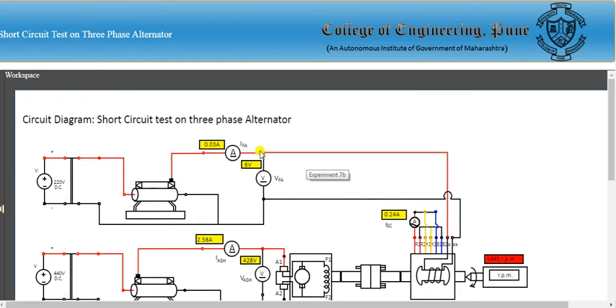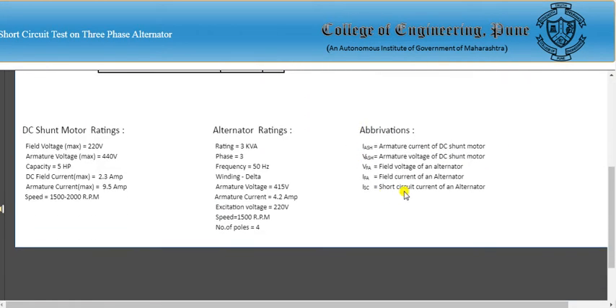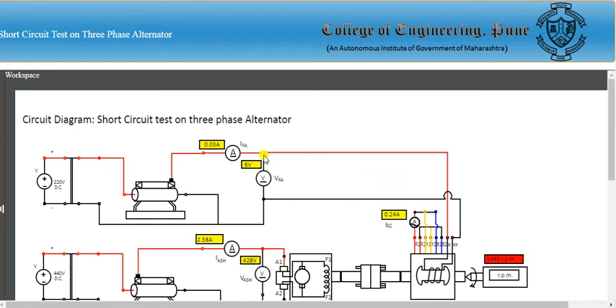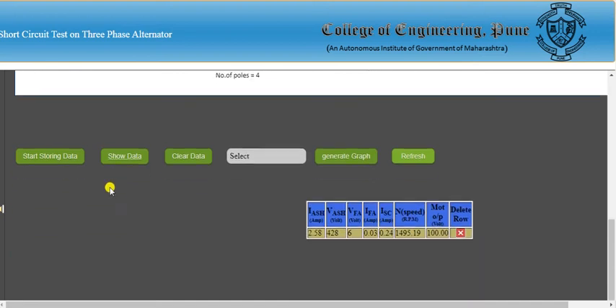The DC field current is increased until the short circuit current (armature current) reaches the rated value of 4.2 A. The alternator ratings are shown on screen — rated voltage is 415 V and rated armature current is 4.2 A. Keep storing and showing data as each new current value is recorded.